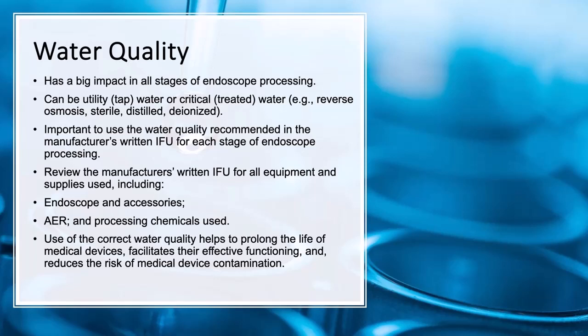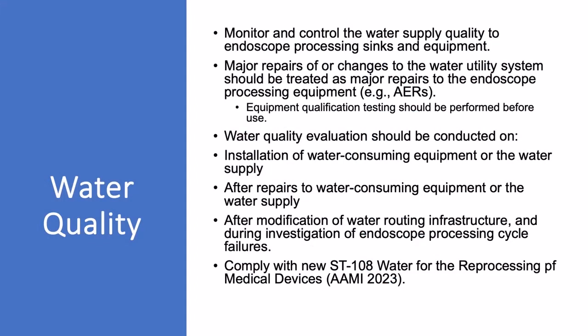Review the manufacturer's written instructions for all equipment and supplies used, including endoscopes and accessories, your automated endoscope reprocessor, and chemicals used. And use of the correct water quality helps to prolong the life of the device, facilitates their effective functioning, and reduces the risk of medical device contamination. Monitor and control the water supply quality to endoscope processing sinks and equipment. Any major repair or changes to the water utility system should be treated as a major repair to the endoscope processing equipment, such as your AERs.